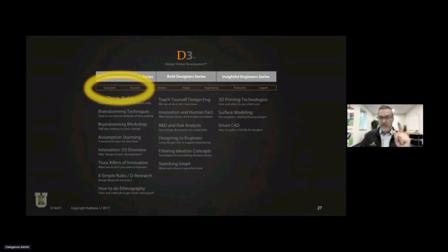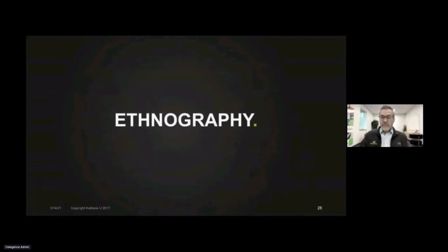But human factors engineering activities begin in phase 0. So some of the things that we would do are ethnography. When we're in phase 0, ethnography is a great tool because in phase 0, we haven't designed a concept yet. There's no prototype to look at. There's nothing. But what we can do is look at what our users are doing now with perhaps a predicate device, and how they are operating in this scenario, what's working and isn't working for them, what's difficult. That's what ethnography does.